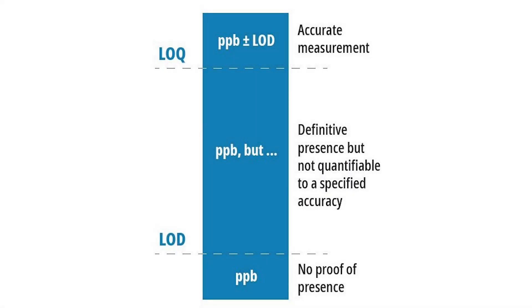So the limit of detection is the point at which you can say definitively that you have proof of the presence or absence of an analyte — in this case, total chlorine. The LOQ is the point above which your accuracy specifications are valid, so you can accurately quantify the amount of chlorine that's present. Between the LOD and the LOQ, you have proof of presence but can't accurately quantify it yet. I think about fully credible data as being measurement values above the LOQ or below the LOD.